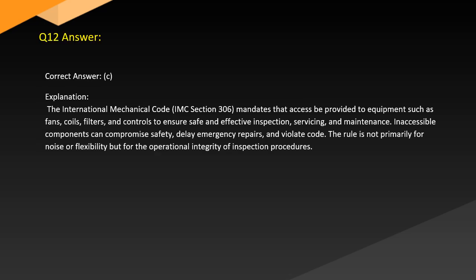Answer. Correct answer: C. Explanation. The International Mechanical Code (IMC) Section 306 mandates that access be provided to equipment such as fans, coils, filters, and controls to ensure safe and effective inspection, servicing, and maintenance. Inaccessible components can compromise safety, delay emergency repairs, and violate code. The rule is not primarily for noise or flexibility, but for the operational integrity of inspection procedures.